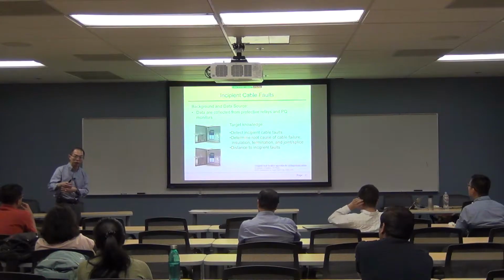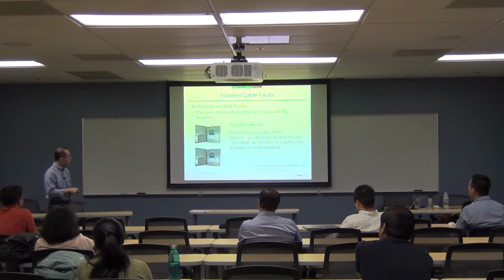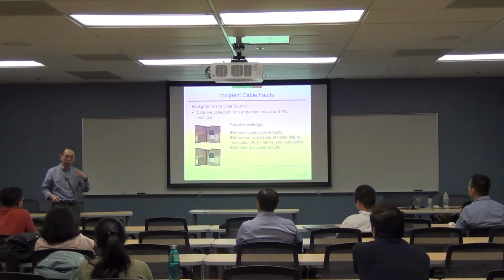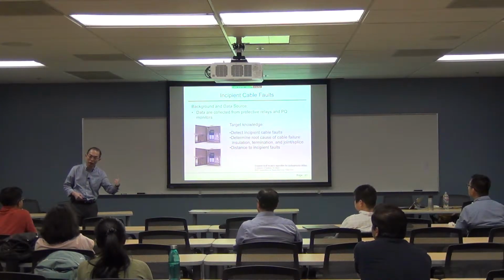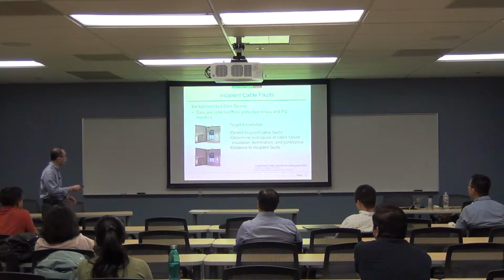Most of the time failures happen at the splice, because that seems to be the weakest link. We'd also like to estimate the distance to the incipient fault, the fault that's still developing. I'll show you the first one and the last one, not the one in the middle.